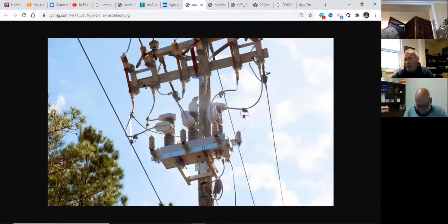Where I'm headed here, guys, is overhead has temporary faults - tree limbs, birds, animals, whatever, that have the capability of falling away and clearing themselves. Underground faults are permanent. They don't fix themselves. When you have underground wire or underground equipment, if there's a fault on it, it will not clear itself. That's a good application of a sectionalizer: fault occurs one time, sectionalizer opens. That's why we use sectionalizers. Does that make sense to everybody?